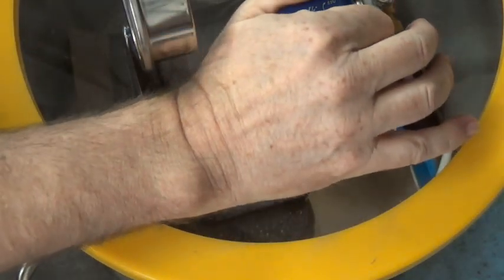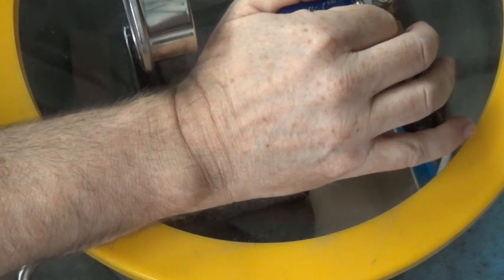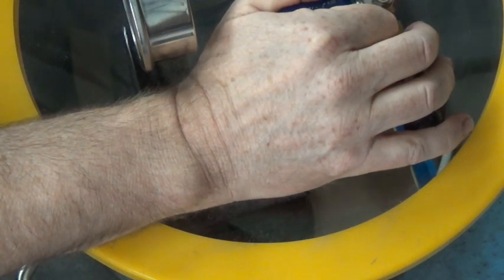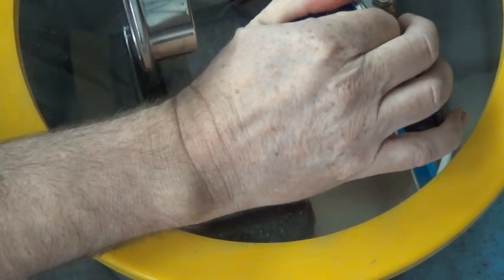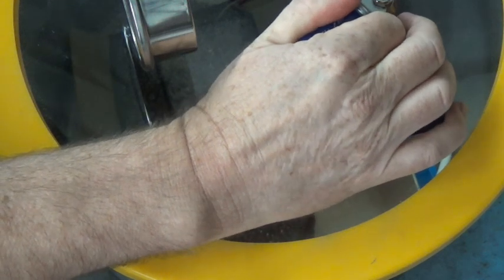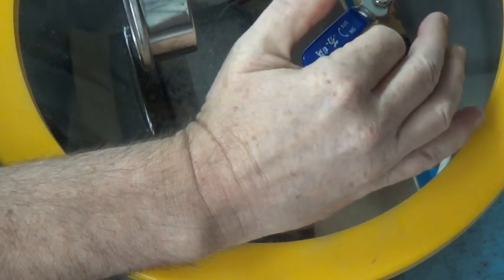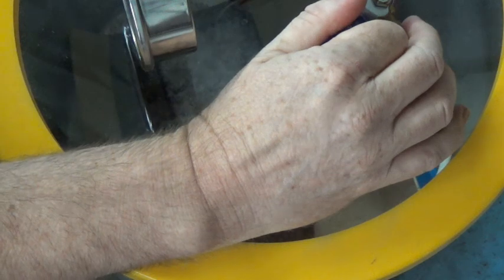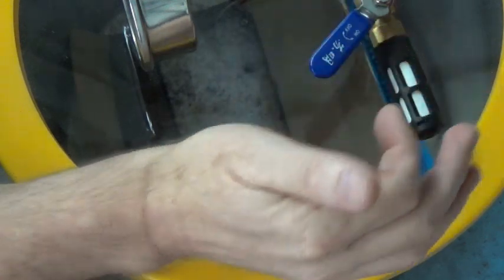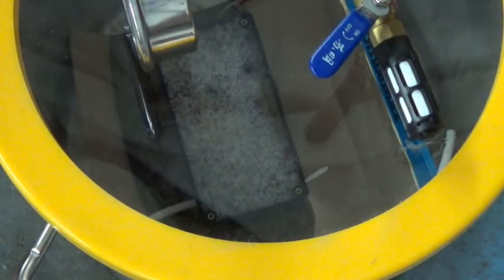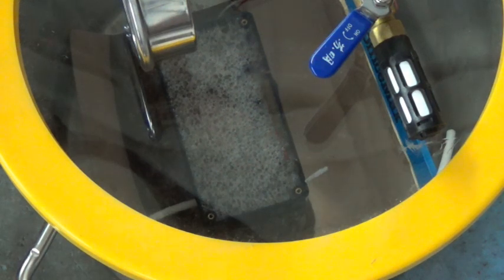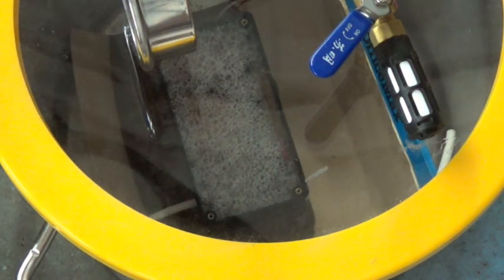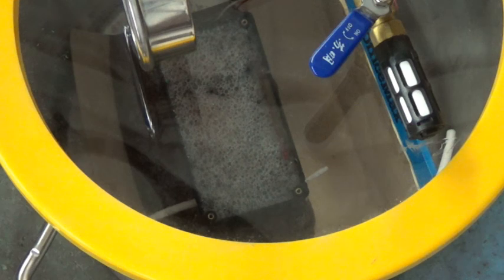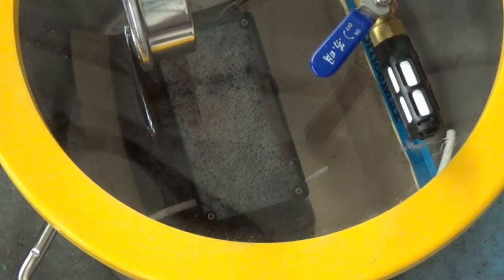Okay, let's just crack open the valve a little bit. You don't want to open it up all the way because depressurization will cause the cell guard to flow out of the kit box from air pressure entering the chamber. It'll squirt that cell guard out all over the place. I've done it before. I've learned from experience. So we just crack the release valve open just a little bit.